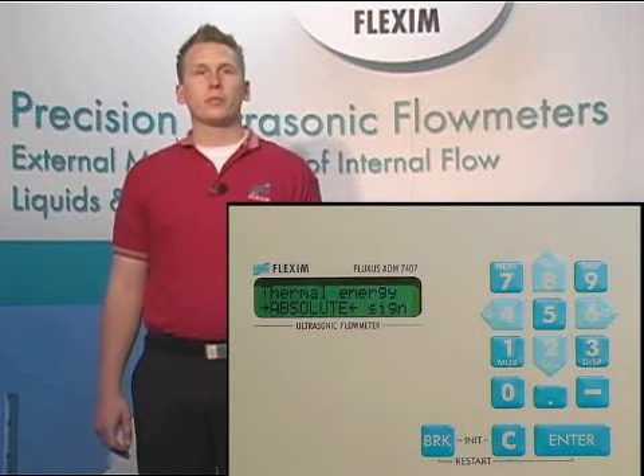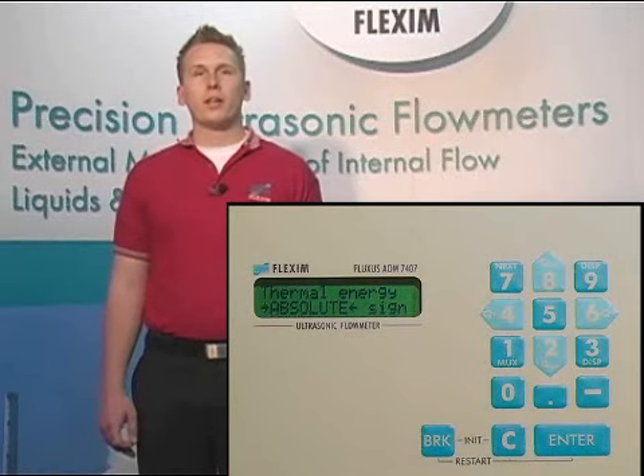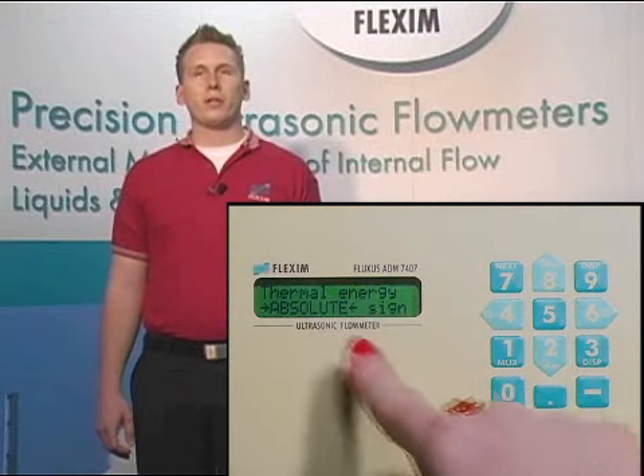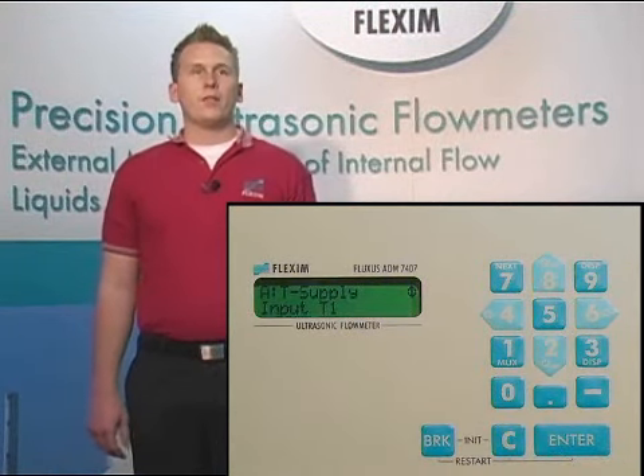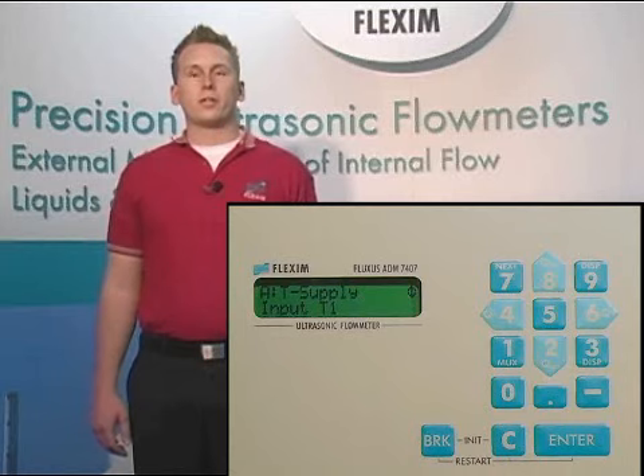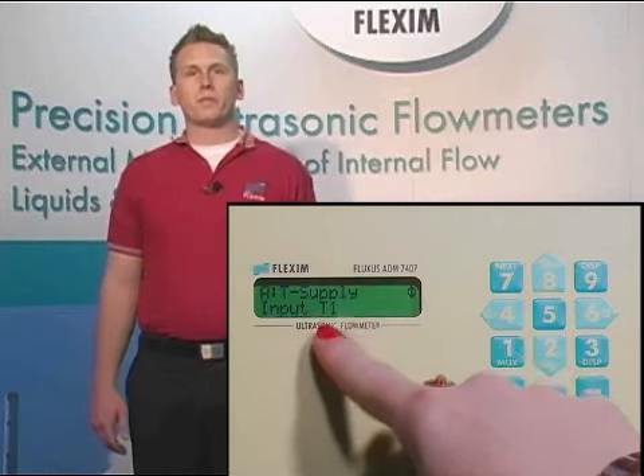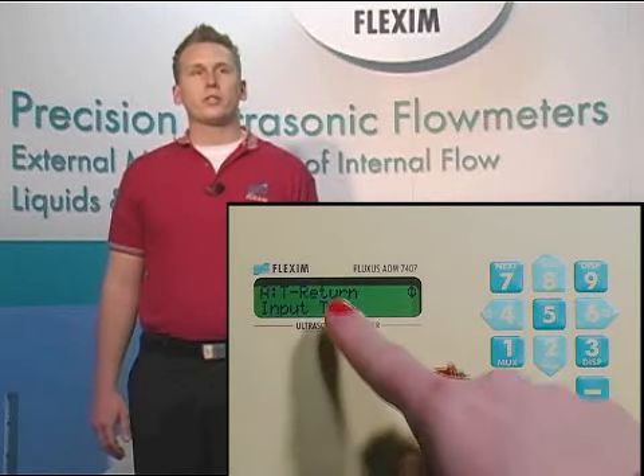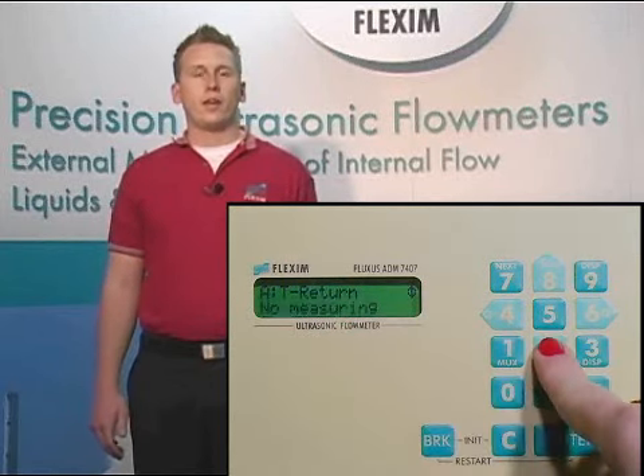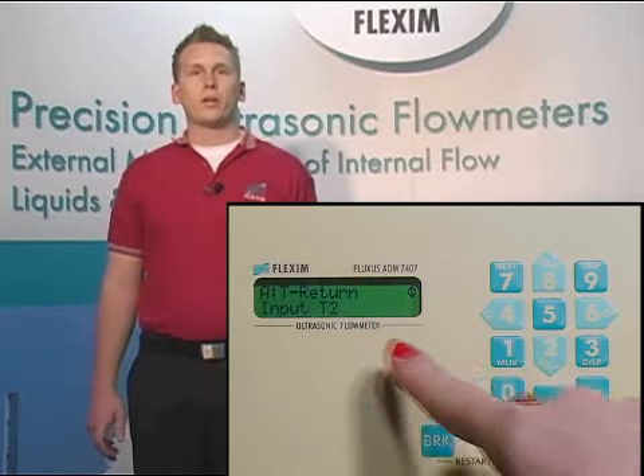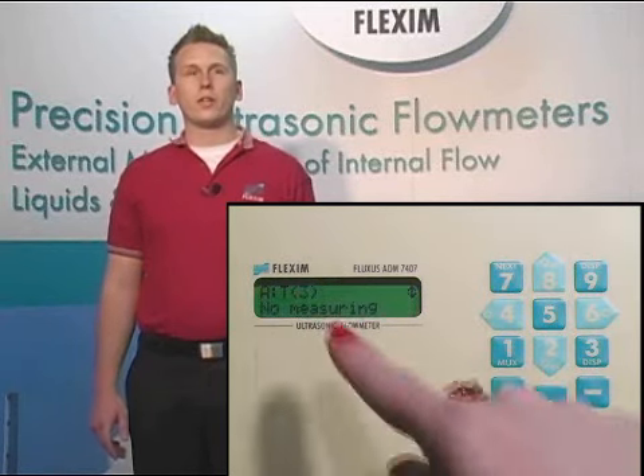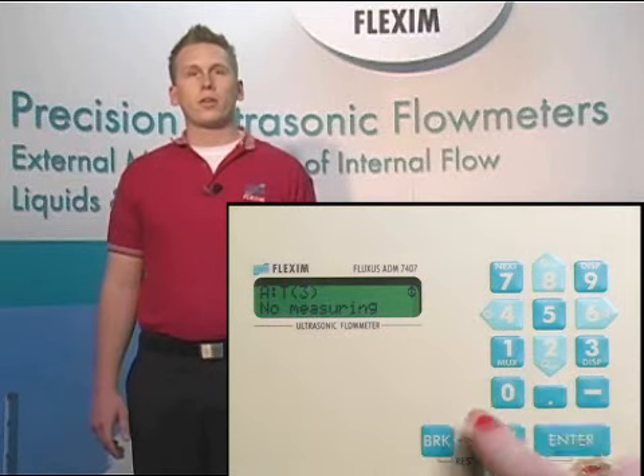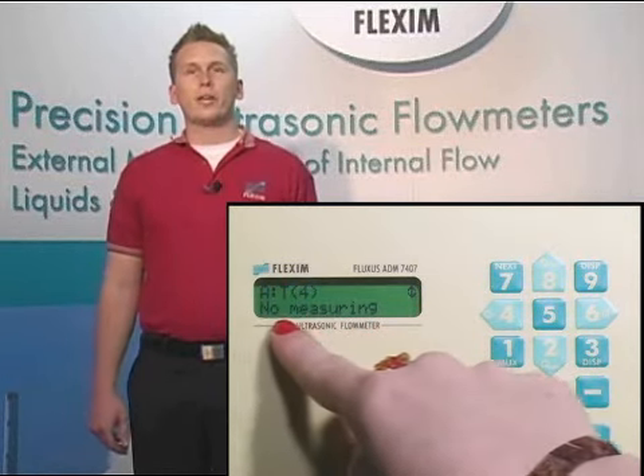We now have a prompt for absolute or sign. This allows us to show a negative value for our energy rate if our temperature RTDs are mounted backwards. Most people generally leave this on absolute. Next, we get to choose how to measure our supply and return temperatures. Assuming we're using RTDs on both supply and return, scroll to input T1 for supply, hit enter, and then scroll to input T2 for return, and hit enter to confirm. We can also simply skip T3 and T4, leaving them at no measuring, and hitting enter on each to confirm them. Now we can hit break to escape from this menu since we've done everything we need to here.